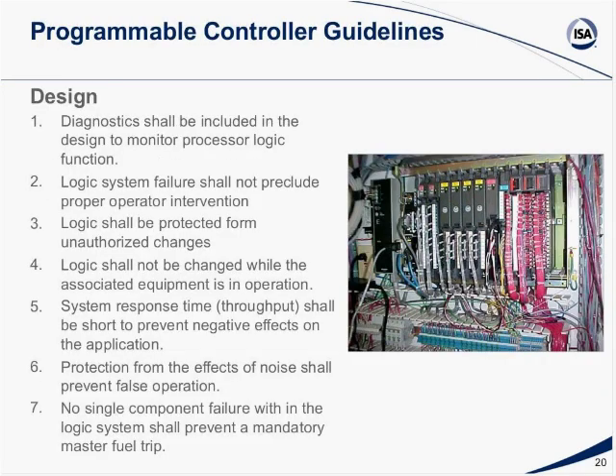Now I'm going to talk a little bit about your programmable controller guidelines, or logic solver, whatever you may call it. Diagnostics shall be included in the design to monitor process and logic function. This is a problem that some of your lower cost systems do not address. They do not have the built-in diagnostics that you need. The logic system should not preclude proper interface. Logic shall be protected from unauthorized changes. Logic shall not be changed while the associated equipment is in operation.